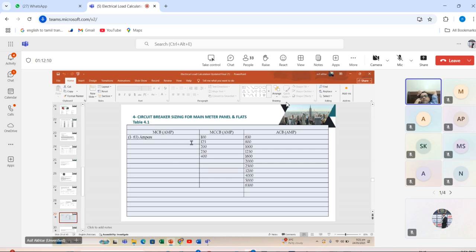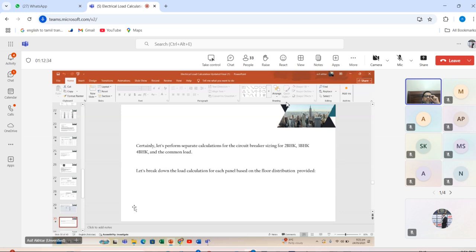Circuit breaker sizing for main panels and flats. In this webinar we have used MCB, MCCB and ACB breakers. So there are three types of breakers used in this kind of distribution. Now, let's perform separate calculations for the circuit breaker sizing for 2 BHK, 3 BHK and 4 BHK, and the common load. Let's break down the load calculation for each panel based on the floor distribution provided.